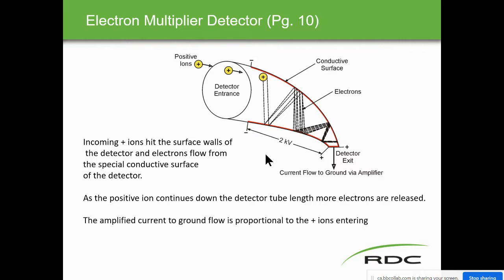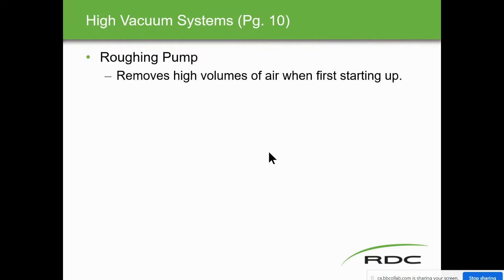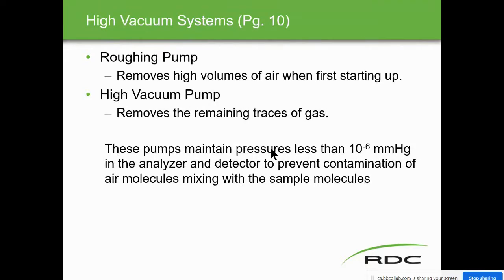The electron multiplier detector: the positive ion enters and bounces along the conductive surface walls of the detector tube, losing electrons with each bounce. There is 2,000 volts across the detector tube. As the positive ions continue down the tube, more electrons are released from the conductive surface and flow to the detector, generating a current to ground via an amplifier. The amplified current flow to ground is proportional to the positive ions entering.